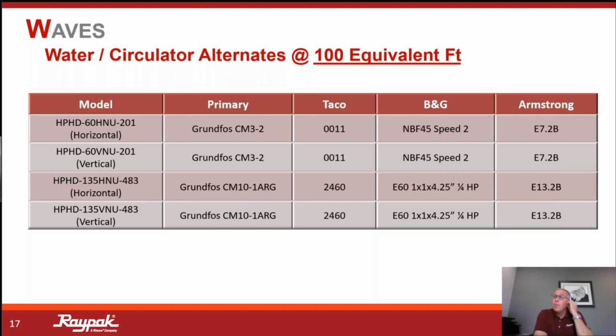Circulators, again, back on task here a little bit. We are offering the Grundfos circulator, but we do have options. Again, based on flow and delta T's, we do have some other pump options that have been vetted by our engineering team, and I do have them listed here. Now, be aware, and this gets into the application side: the heat pump itself potentially can be located outside, and that will elevate those available ambient air temperatures, but then maybe our storage tank is a certain distance away, right? That might be a very plausible factor in our different applications. It might be on a different floor, different elevation. So circulator selection is going to be very important.